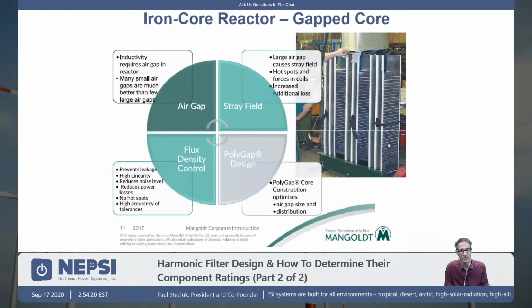This is really a picture that can show you just how many gaps you can have within an iron core reactor. And these all need to be supported within the leg structure itself. So by having lots of gaps, it means that you're going to reduce the noise and you're going to reduce the stray flux that you have in the reactor.